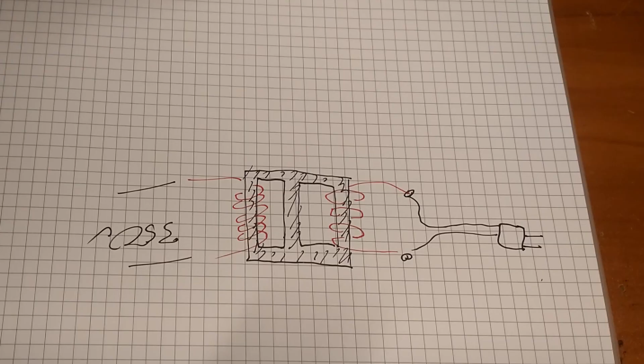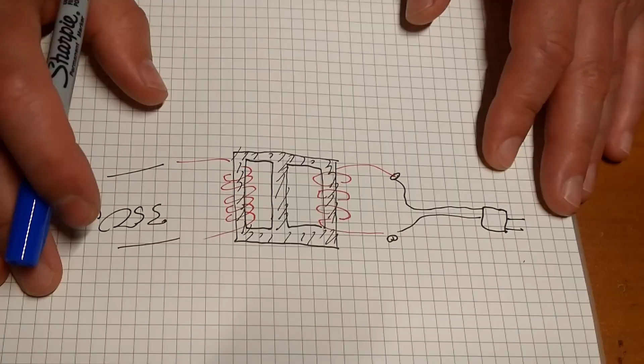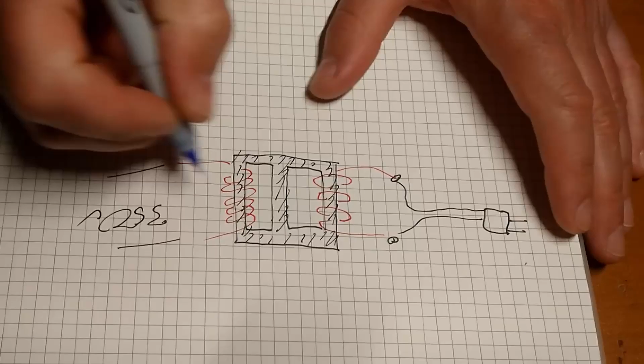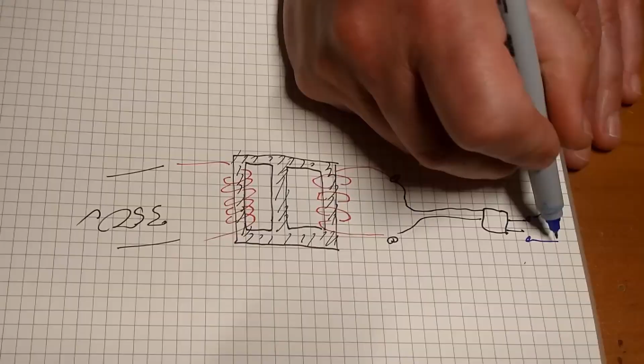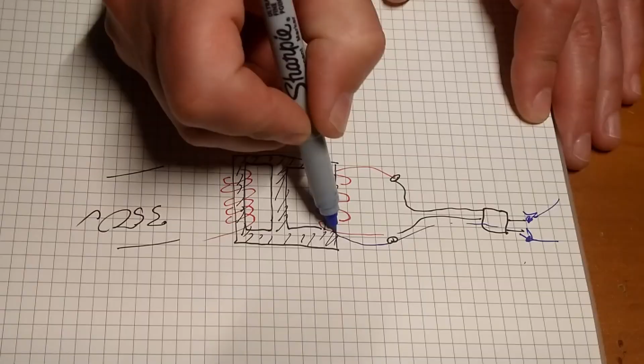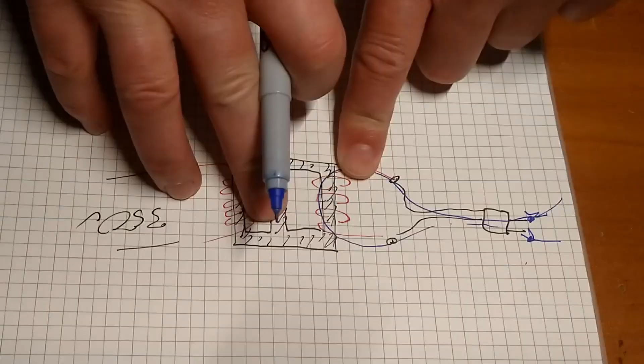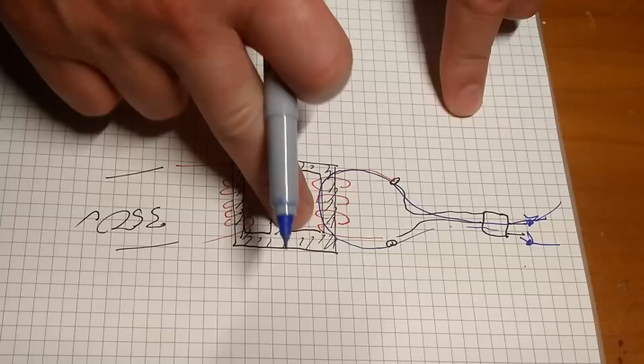So what we need to do is make a measurement with our multimeter. Any old multimeter will do - you can get the cheapest $5 Harbor Freight multimeter as long as it measures DC resistance. We're going to put one probe here and the other probe here, and measure DC resistance. What that will do is show if we have continuity all the way through the winding and back out again. Now, this test doesn't guarantee you have a good transformer or a good winding, but if you do not have continuity, it guarantees you have a bad one. So, the more you know, I guess.